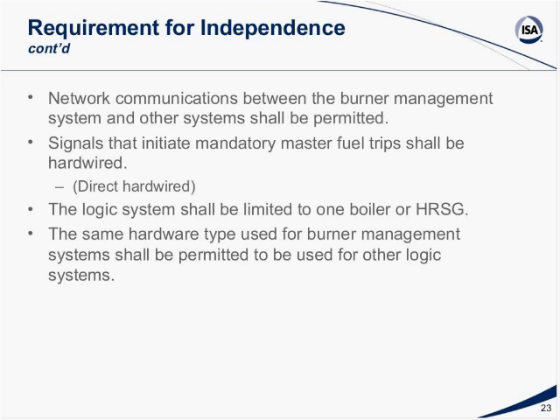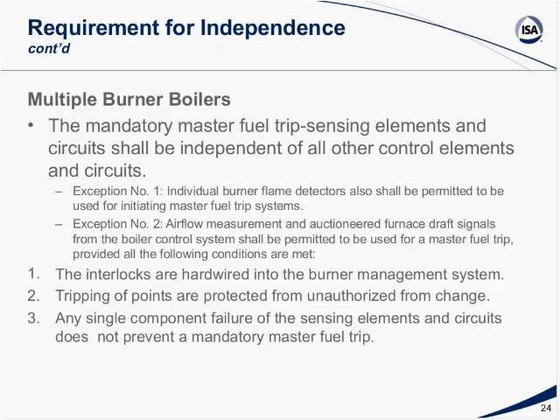The logic system shall be limited to one boiler or heat recovery steam generator. In other words, each boiler or type of boiler must have its independent logic system. The same hardware type used for burner management system shall be permitted to be used for other logic systems. In other words, you can use the exact same system for control and burner management, but they need to be two separate systems. You can use the same ones as long as they meet the requirements. This is a little bit more about requirement for independence. The mandatory master fuel trip sensing elements and circuits shall be independent of all other control systems.